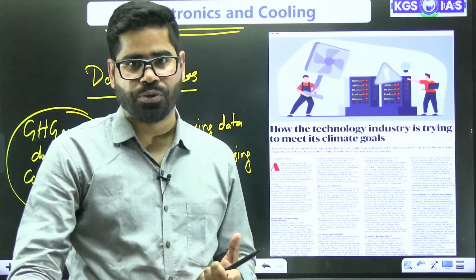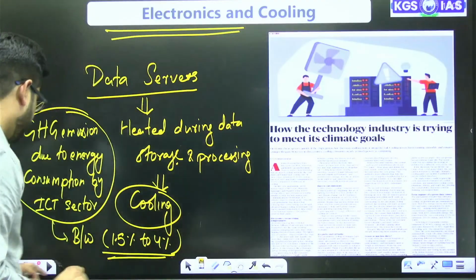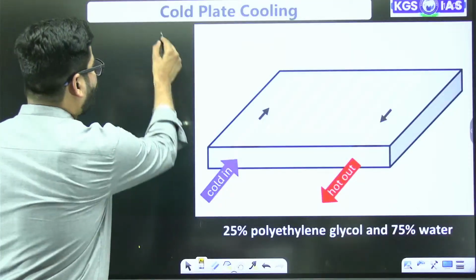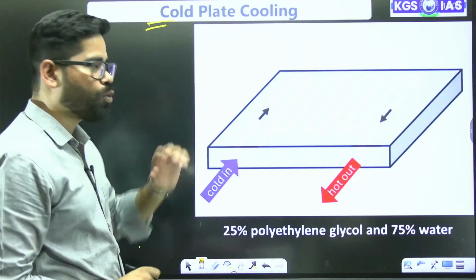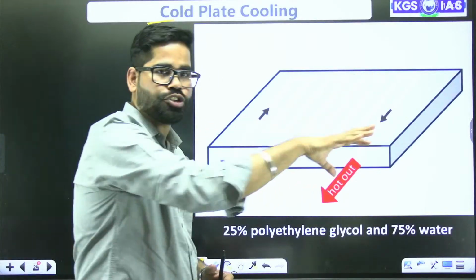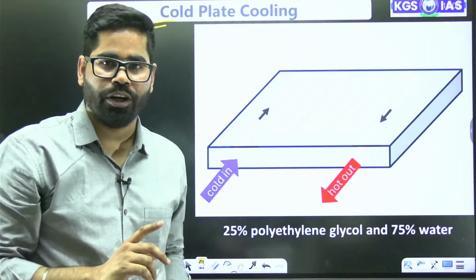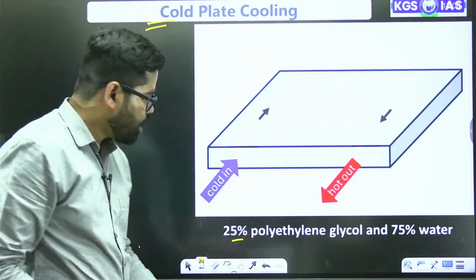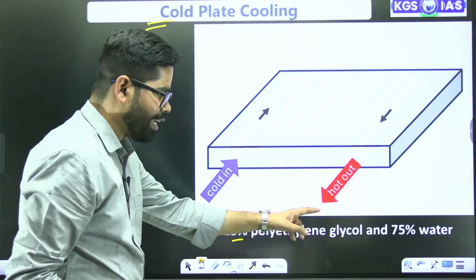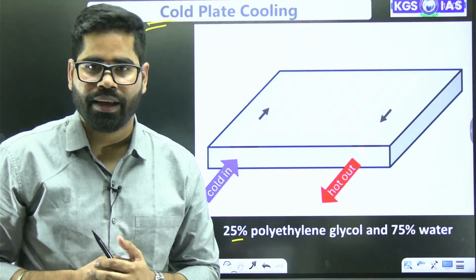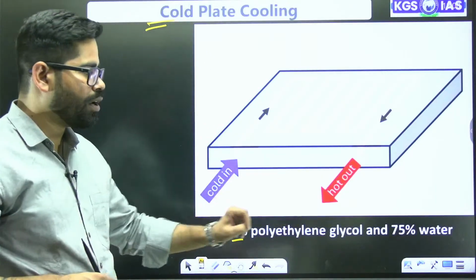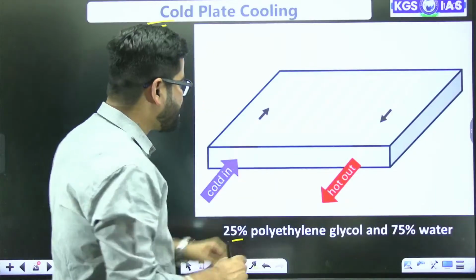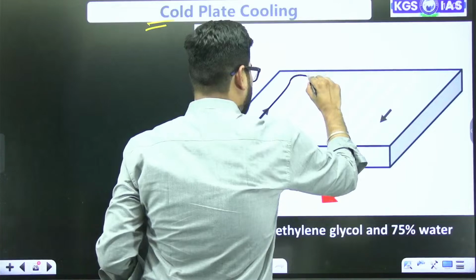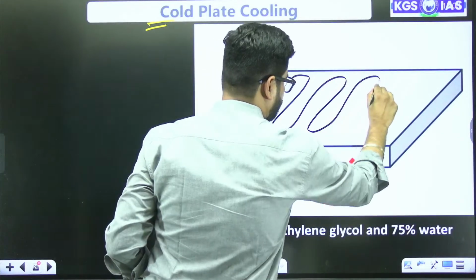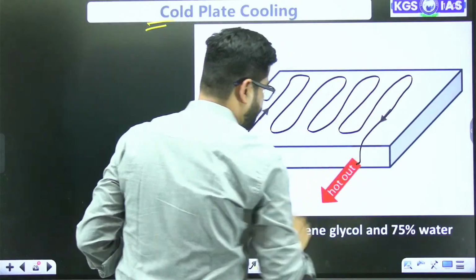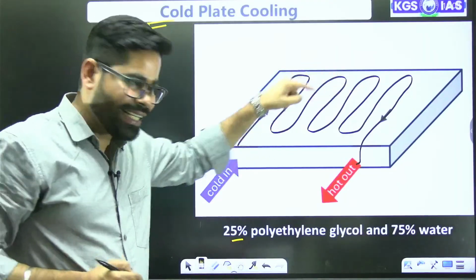So what methods are used here? There is one thing called cold plate cooling, where these plates are installed in the data servers. These plates contain a liquid — 25% of that liquid is polyethylene glycol and 75% is water. This liquid runs through pipes; you can see the pipes passing through here, containing these liquids.